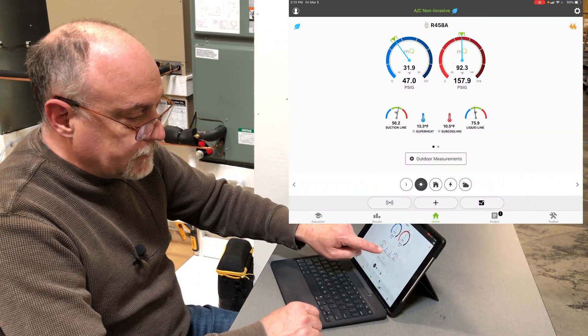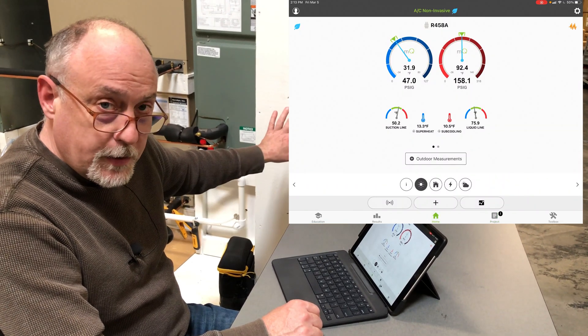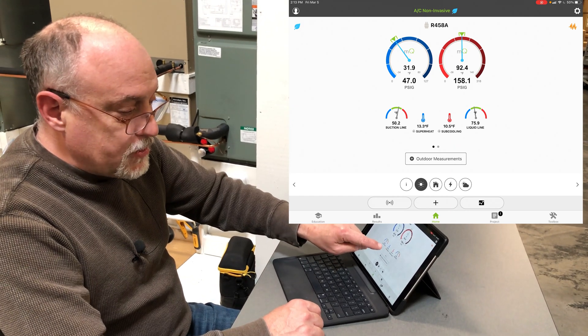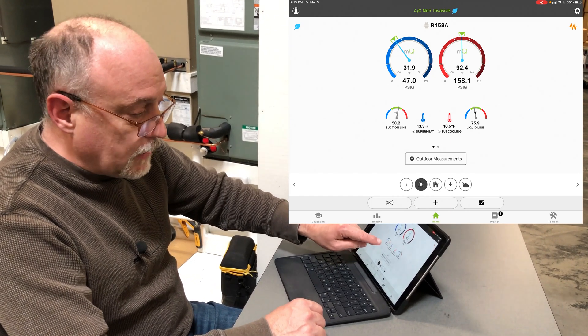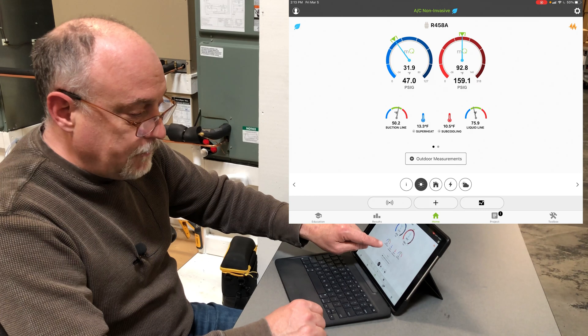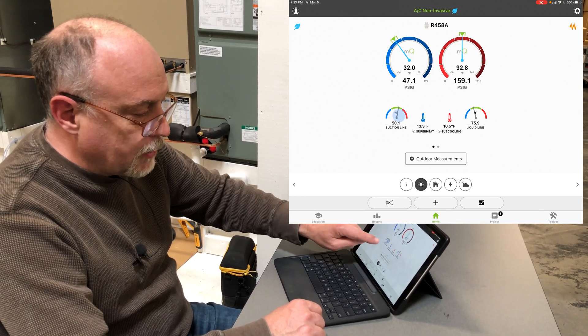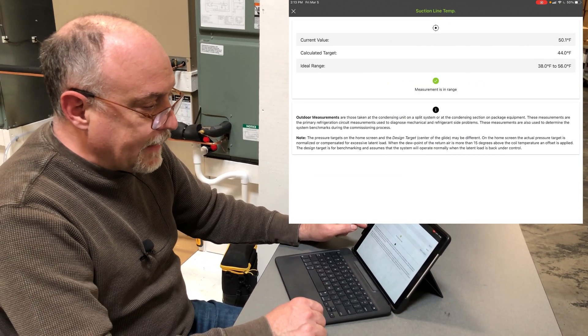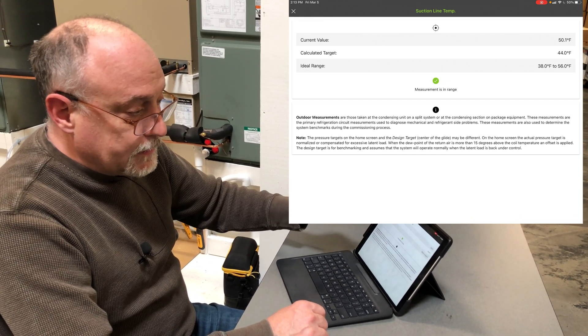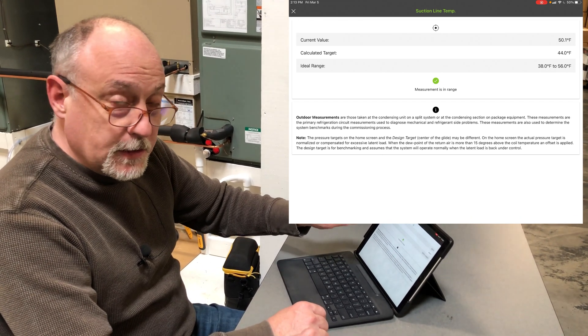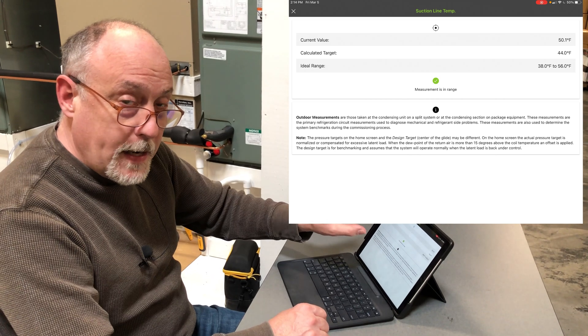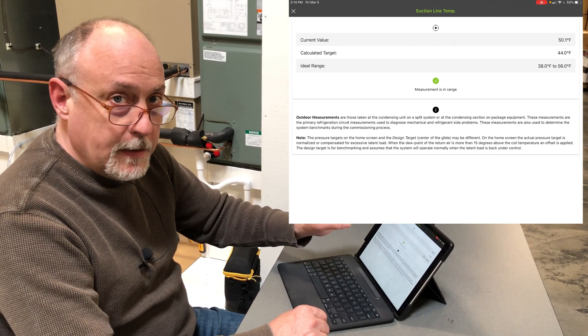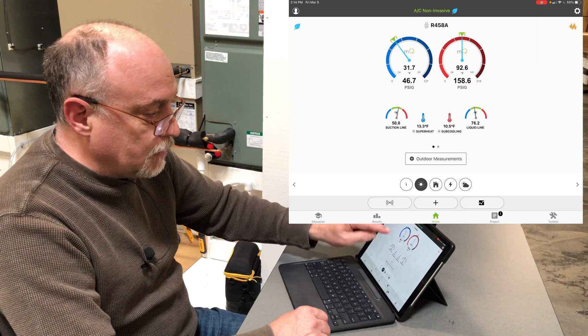Based upon these return air and outdoor air conditions and these subcooling and superheat targets, it's looking for a suction line temperature of 50.2 degrees and a liquid line temperature. We'll tap on the target. It's looking for a calculated target of 44 degrees, plus or minus from 38 to 56 degrees because it's a TXV, so it's got a wide range.